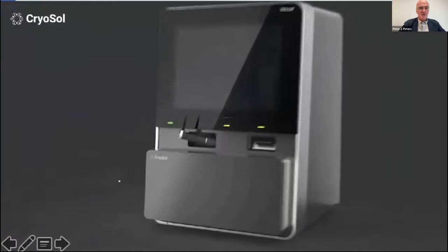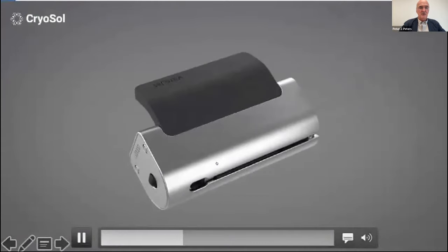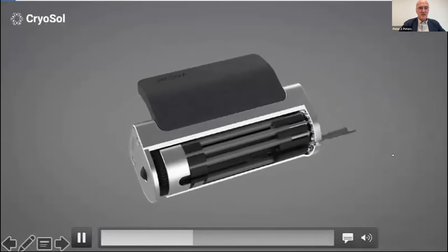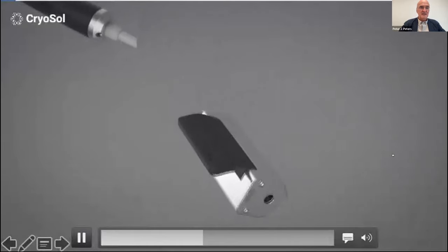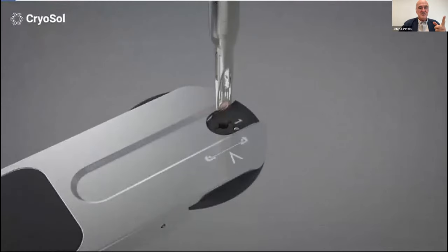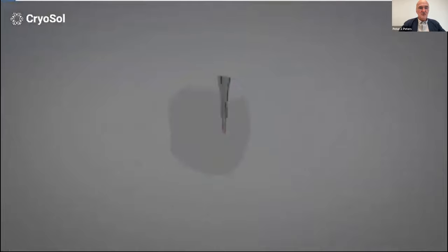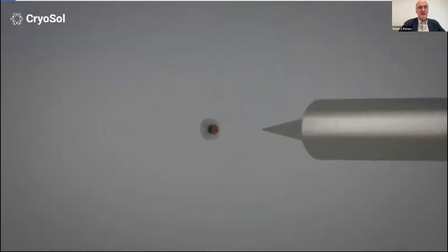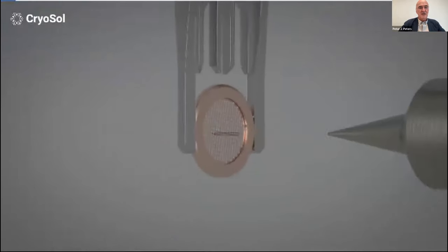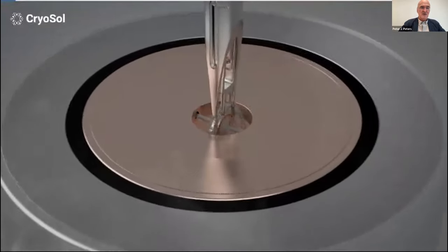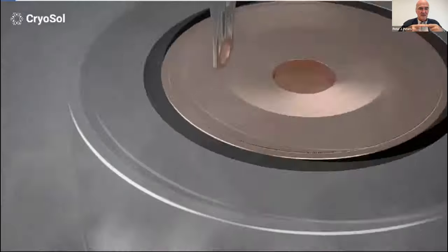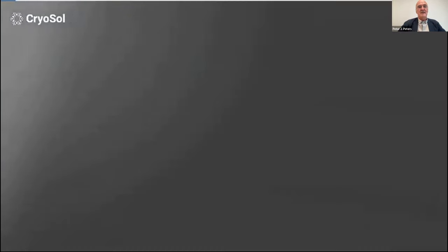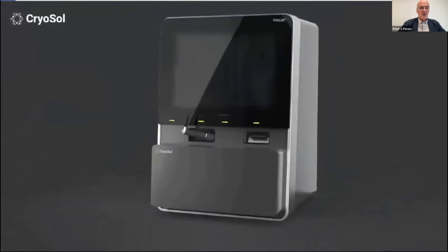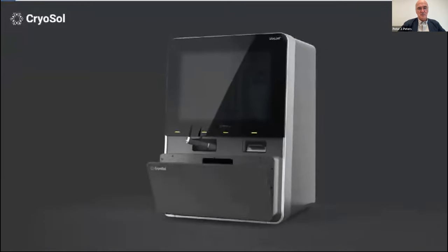You take a purified protein solution, and here is the pin drum. The pin drum has 12 pins, and you take one pin that is meant for the writing. You have 12 grids, auto grids already ready to use. You go to a glow discharge device in the instrument to clean it up and make it hydrophilic. You take a nanoliter or less of medium, you write on the grids, and as fast as possible, you try to vitrify this by the jetting principle that I mentioned earlier. And then it goes to a cassette where you can keep it for months until you want to put it into the microscope.